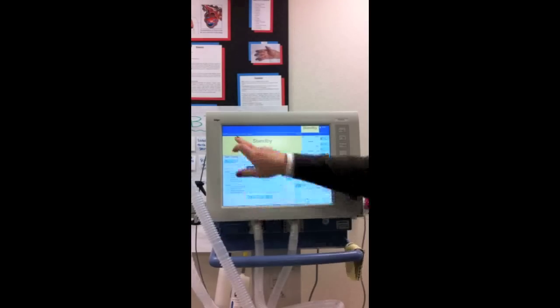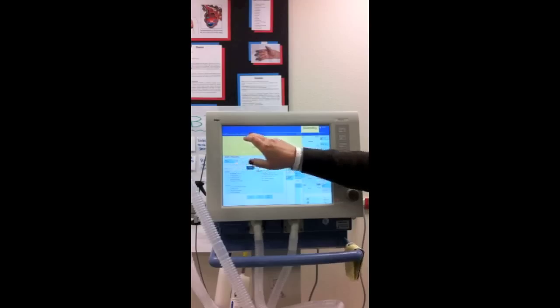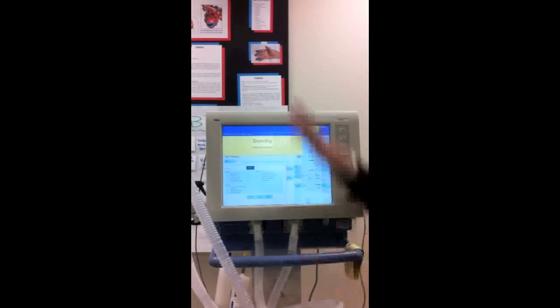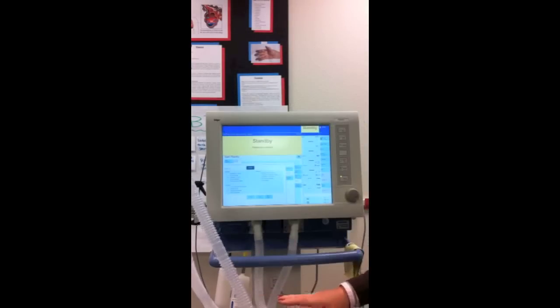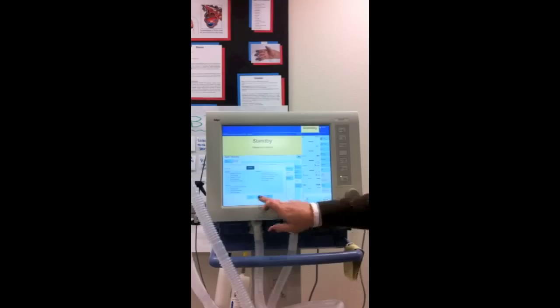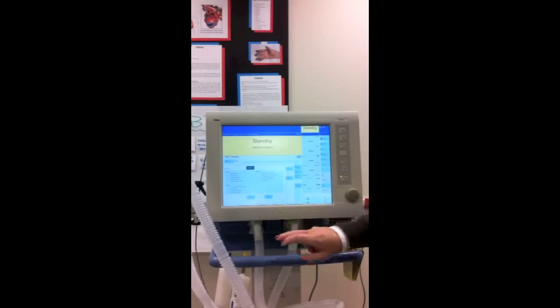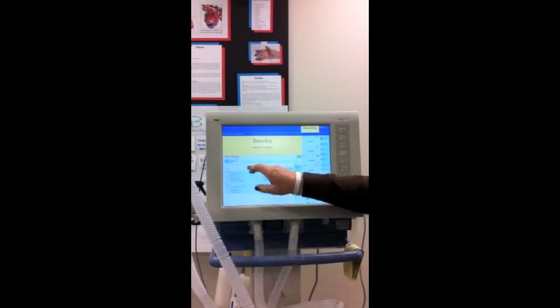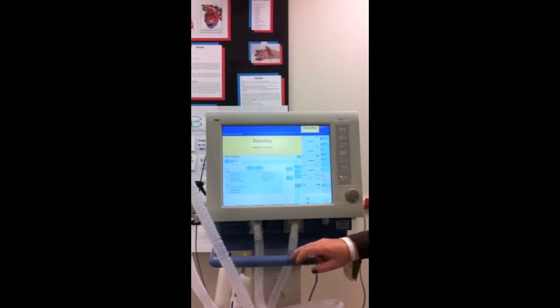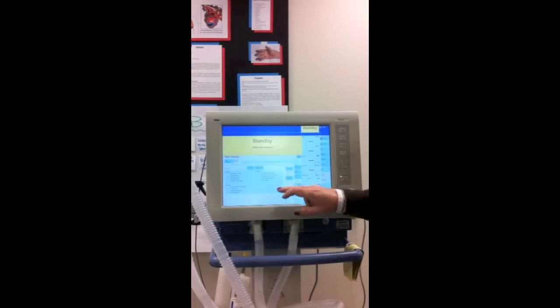So now we're going through and it's saying neo flow sensor placed at the Y piece. We're going to say no because we do not have a neonatal flow sensor, because we're not ventilating neonates right now. So we're going to say no. And then we're going to go to next test. And then you do check. Hold on, it went too far. I'm going to start this over.